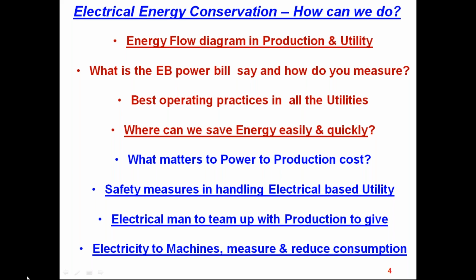So the electricity bill ultimately will give you the best operating practices in the utilities if the utilities are monitored at their endpoint. We can see where all the Bureau of Energy Efficiency says only one point. Any motor above 10 HP operating for 2 shifts, let us say 6,000 hours in a year, definitely needs monitoring, and you provide the basic minimum KWH meter, which is just costing only 2,000 rupees. It has to be installed on all the motors, on all the machines above 10 HP.